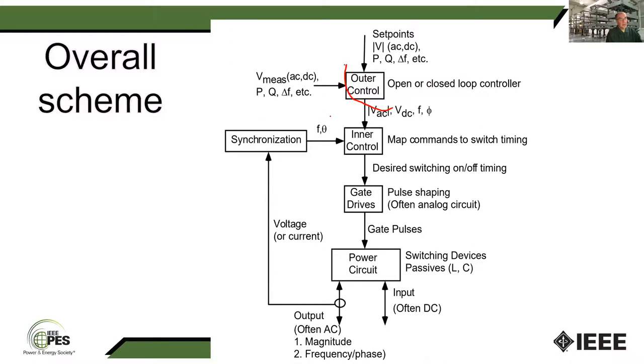And so for something like a PV inverter or a wind turbine, most of the time they're going to be running at unity power factor because they don't benefit from supplying or consuming reactive power, because in most cases where they're connected, there's no market for it. And there's no penalty if they operate at unity power factor.